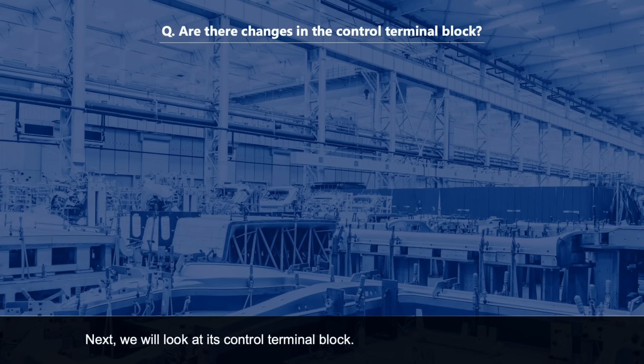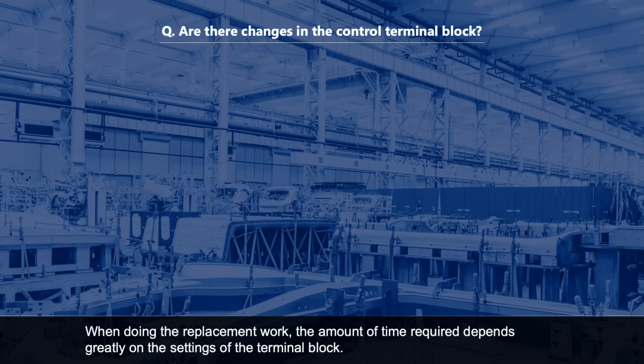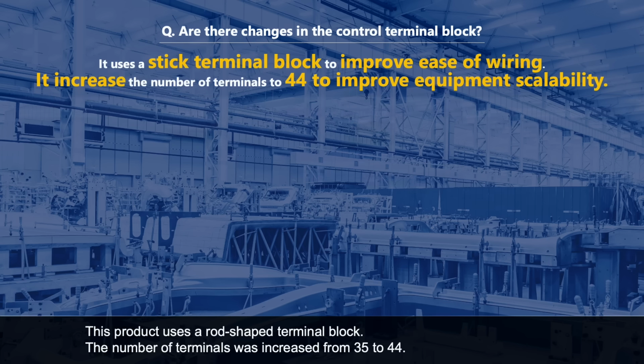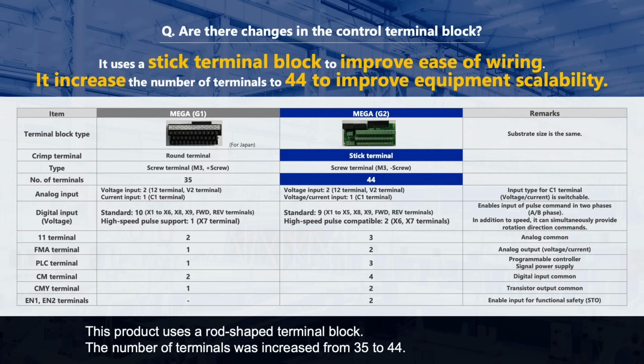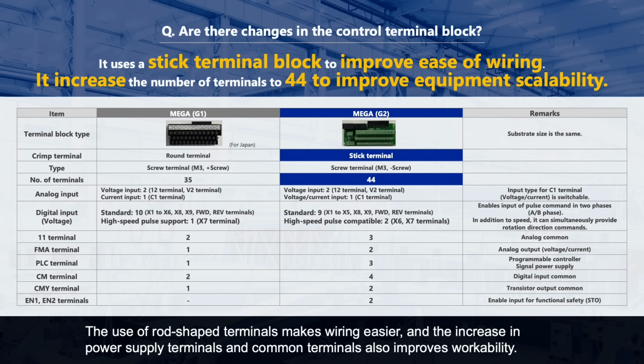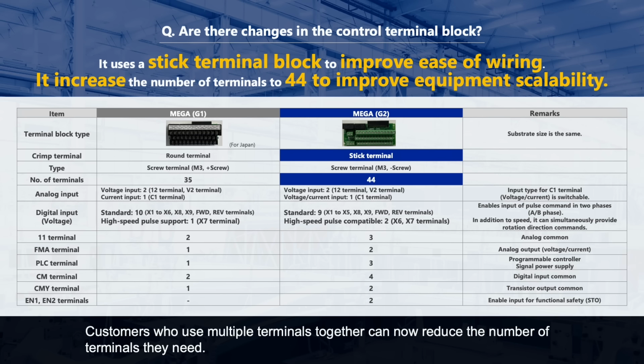Next, we will look at its control terminal block. When doing the replacement work, the amount of time required depends greatly on the settings of the terminal block. This product uses a rod-shaped terminal block. The number of terminals was increased from 35 to 44. The use of rod-shaped terminals makes wiring easier, and the increase in power supply terminals and common terminals also improves workability. Customers who use multiple terminals together can now reduce the number of terminals they need.